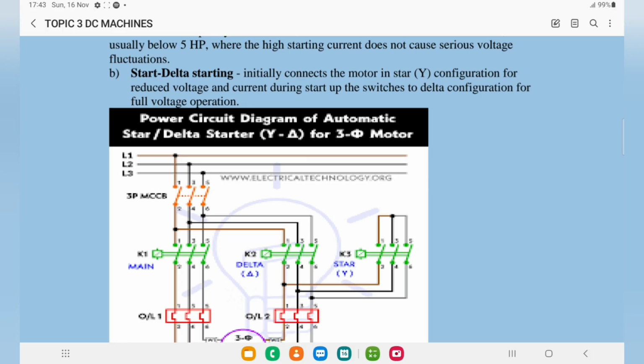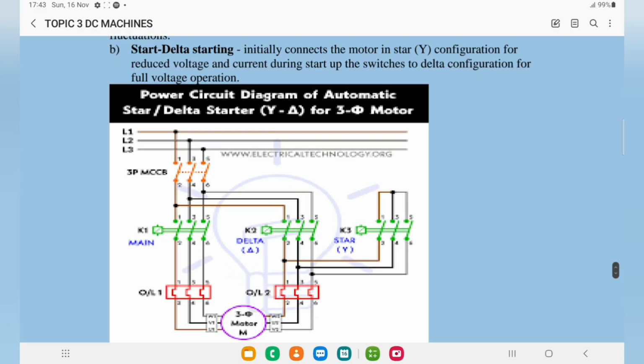So we have the power circuit diagram for a star, and here we are feeding the motor with a star connection. If you look at it, we have three phases, phase 1, phase 2, and phase 3, passing through a three-phase MCCB. There's also a contactor, which is the main contactor. It passes through an overload relay to power the three-phase motor. And there is also the delta side, where you'll have to look at how the connection is made. It is not the same as how the connection is made on the star side.